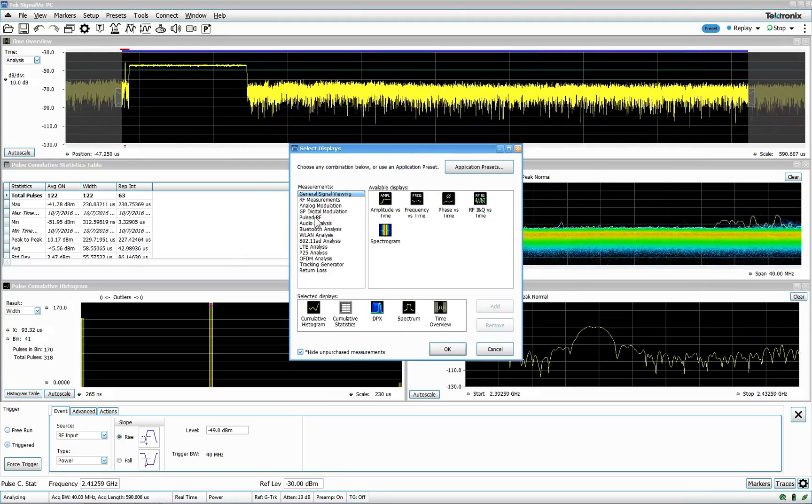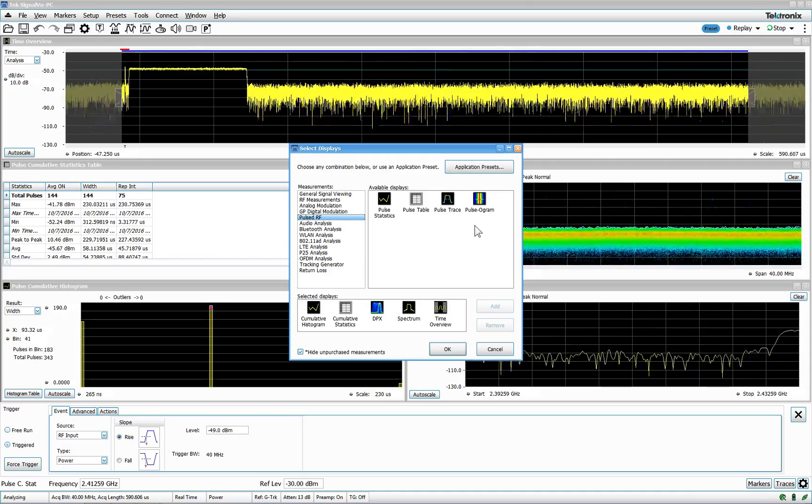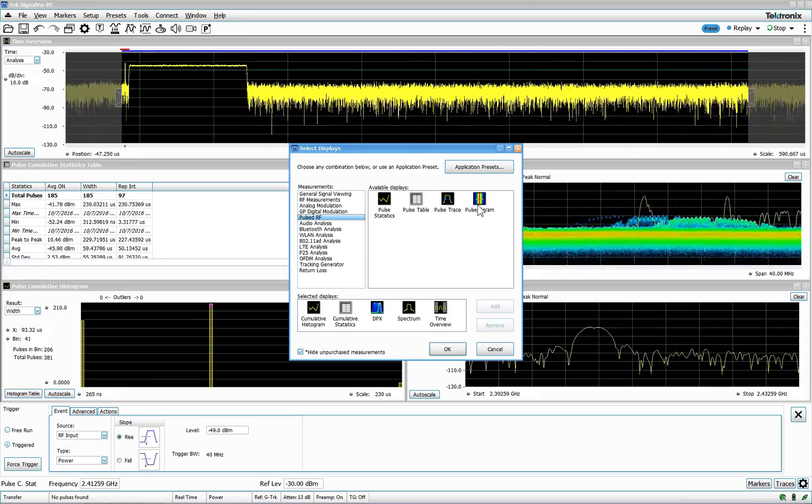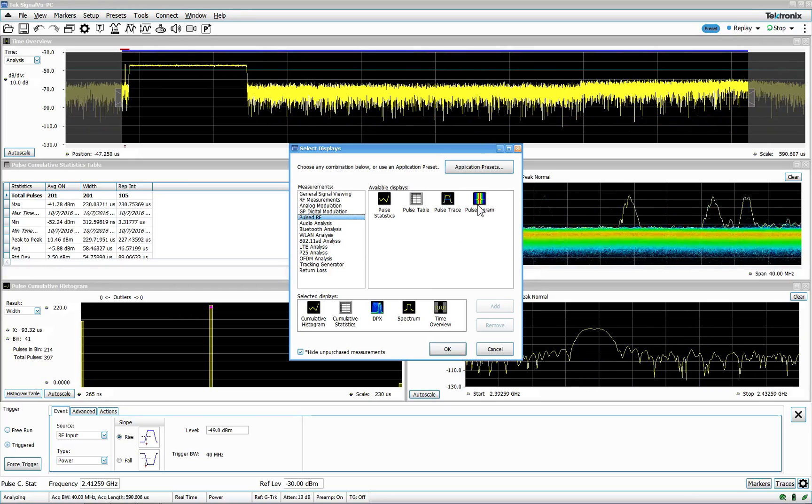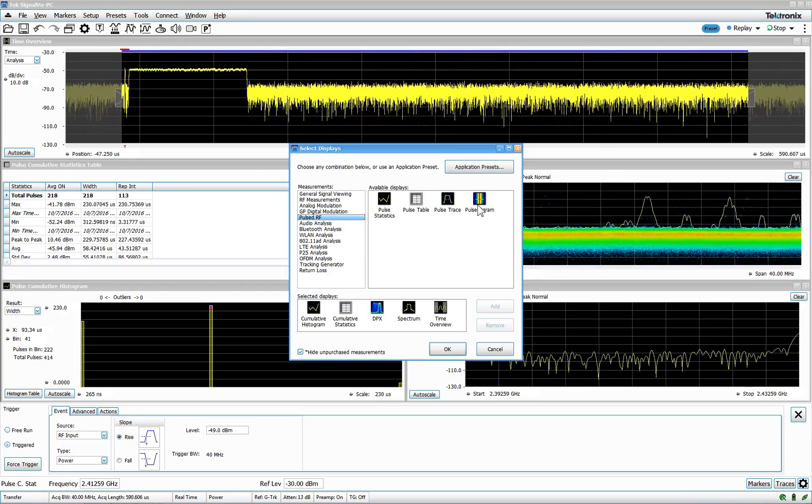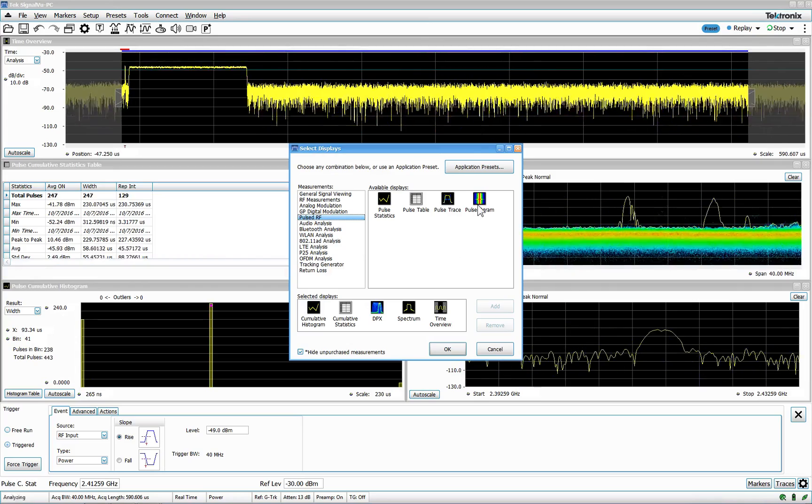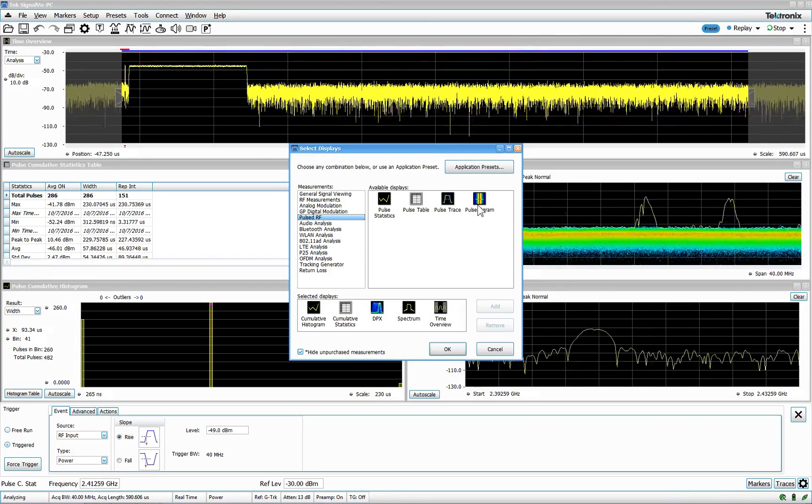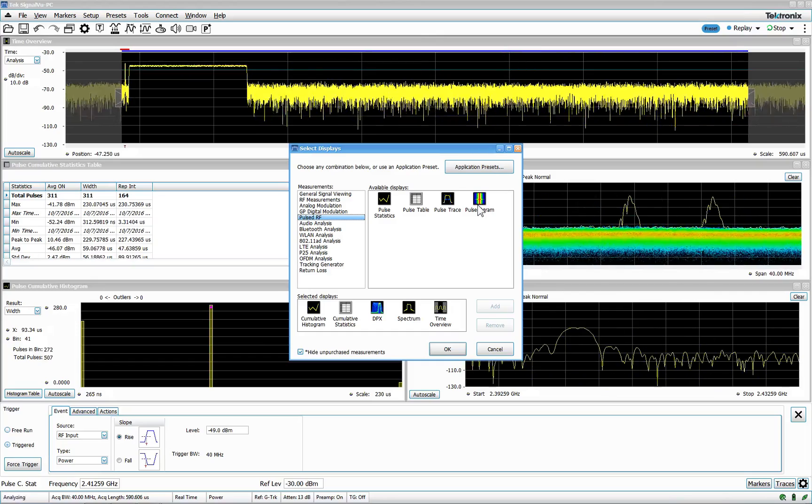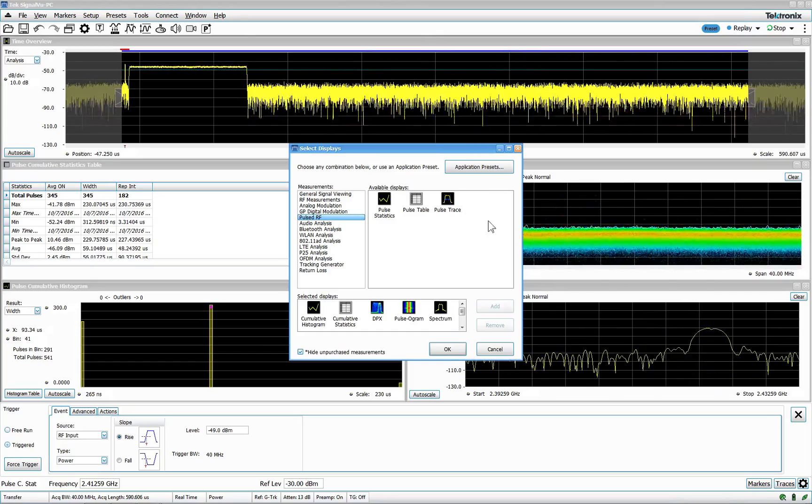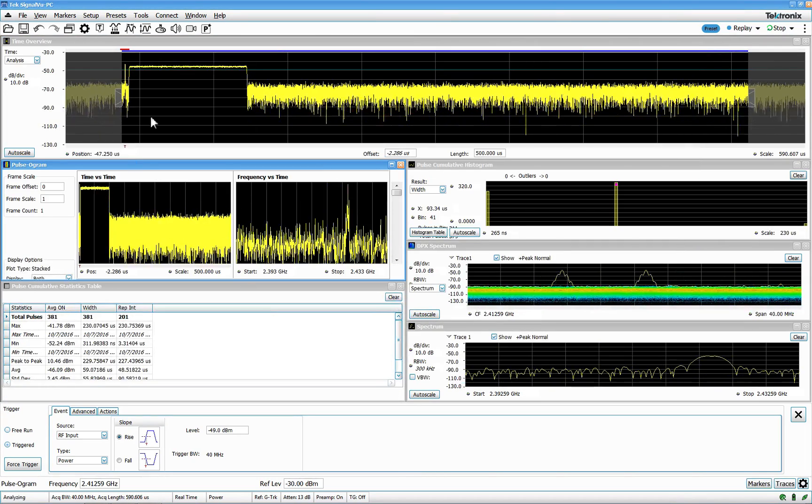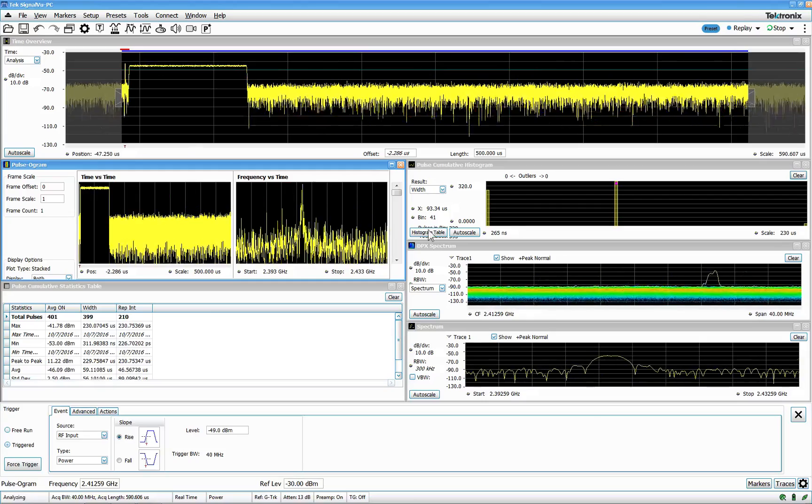And the last one here, I would not spend too much time on, it's the pulseogram. It's when we do fast frame, when you actually capture only part of the acquisition but do that many times. So we have 10,000 pulses without the dead time between the pulses. That's very useful. When I just run it here, you will see it looks like a mix between a time overview and spectrum. That's basically this and this down here. But if you have multiple, this will be kind of a waterfall.